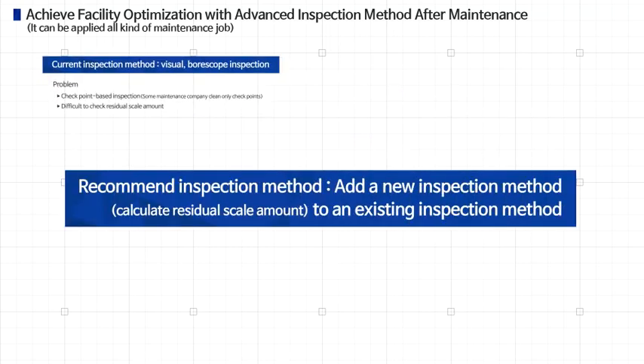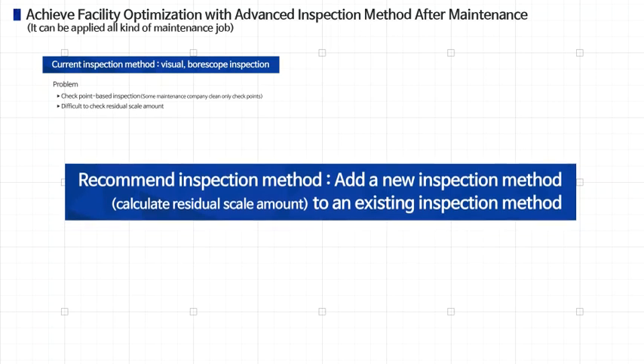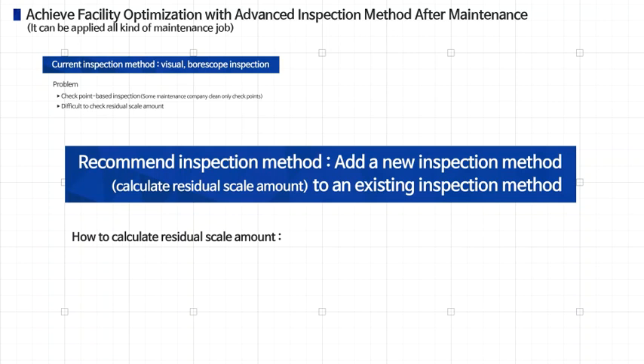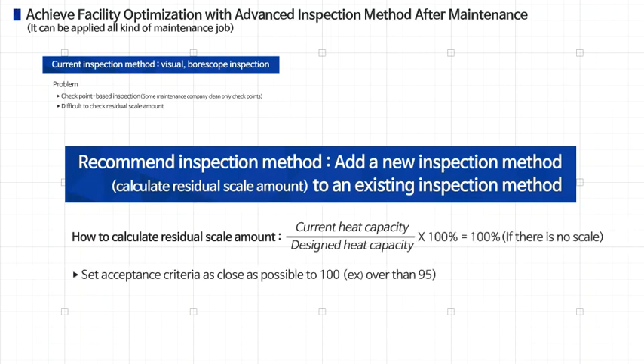To solve these kinds of problems, we recommend an improved inspection method. After the current inspection process, residual scale amount is inspected through the following equation. The calculation is: current heat capacity divided by designed heat capacity, multiplied by 100%. The equation indicates 100% when there is no scale.